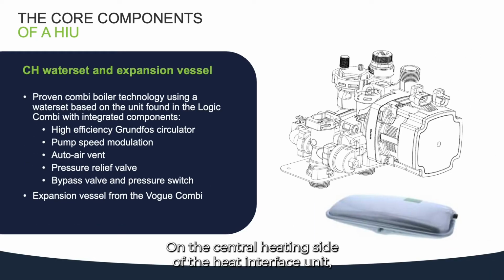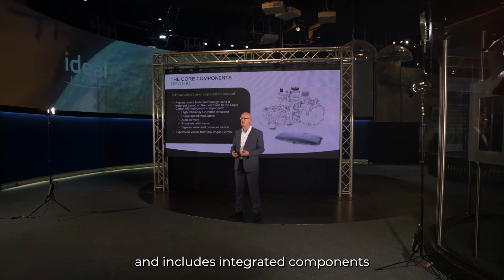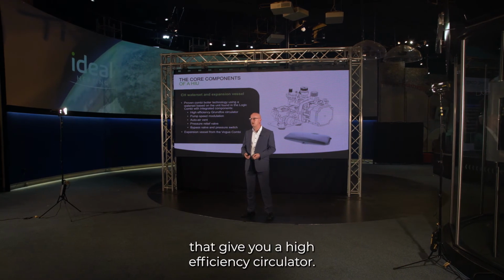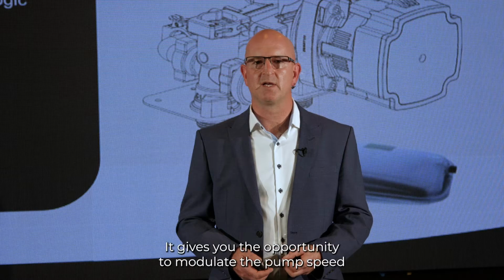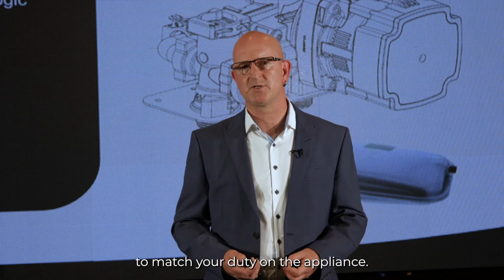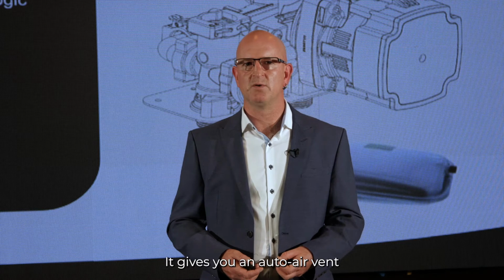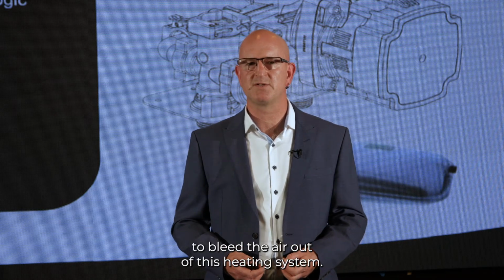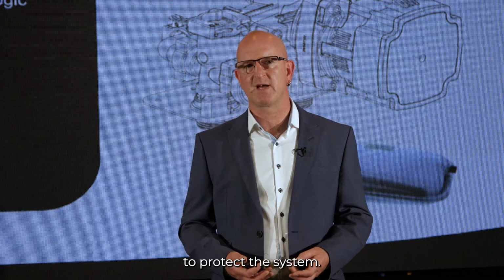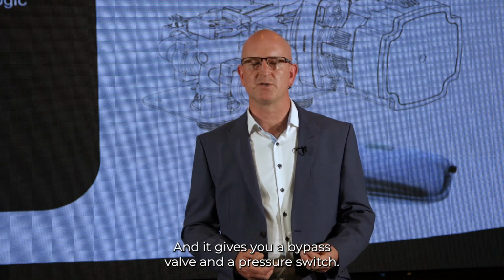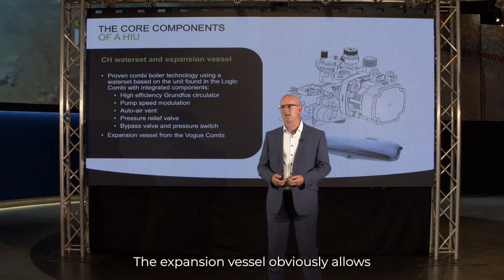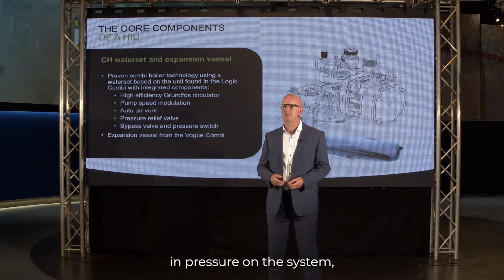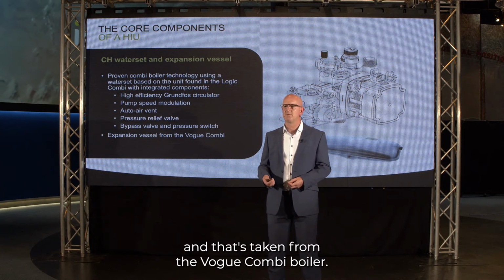On the central heating side of the heat interface unit, you'll see a water set and expansion vessel. So the water set is taken from our highly successful Logic combi boiler and includes integrated components that give you a high efficiency circulator. It gives you the opportunity to modulate the pump speed to match your duty on the appliance. It gives you an auto air vent to bleed the air out of this heating system. It gives you a pressure relief valve to protect the system, and it gives you a bypass valve and a pressure switch. The expansion vessel obviously allows for heating and cooling fluctuations in pressure on the system, and that's taken from the Vogue combi boiler.